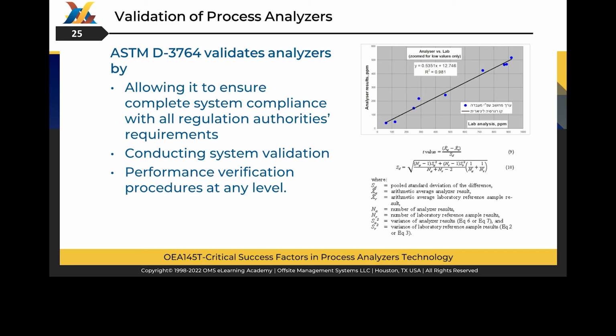Standard practice for validation of process stream analyzer systems, ASTM D3764, describes procedures and recommendations for validating a total process analyzer system, or its subsystems, or both, used to directly measure the physical or chemical characteristics of petroleum and petrochemical products. Validation is achieved by statistical assessment of results generated for common materials by the total analyzer system or its subsystem versus results generated by an ASTM or other established primary test method, or PTM.